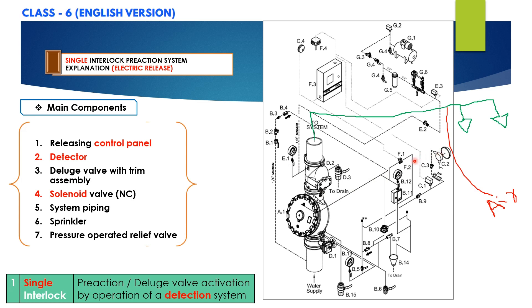Electrical release systems require an electric solenoid valve controlled by an approved releasing control panel with a compatible detection system. In fire condition, when the detection system operates, the system control panel energizes the solenoid valve to open, causing the deluge valve to open. The sprinkler system then fills with water. If any sprinklers have opened, water will flow from the system; if sprinklers have not opened, water will remain in the sprinkler system piping only. A sprinkler head must open before water flows from the system.